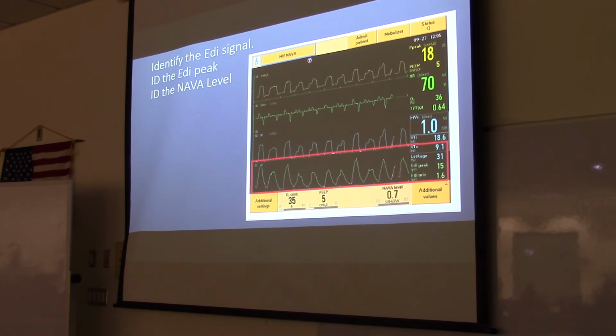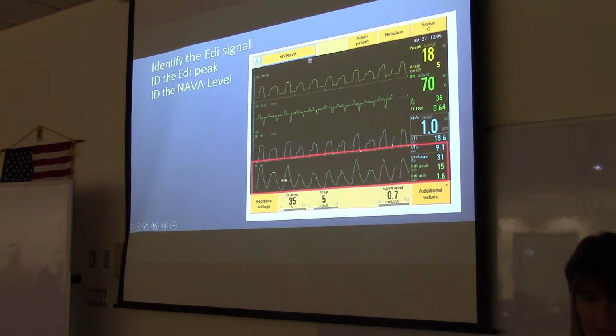Okay, it wants you to identify the EDI signal. And then the EDI peak, and then the NAVA level. So we've got pressure, we've got flow, we've got, oh, it's highlighted in red. Oh my gosh. Okay then, I'm making this really difficult for you guys here. What about EDI peak? Can you see it from where you're sitting? 15. And what is the minimum? 1.6. So when you see 1.6 is the minimum, and you're going to set a trigger of 0.5, you add those two numbers together, and that's when the breath would start.